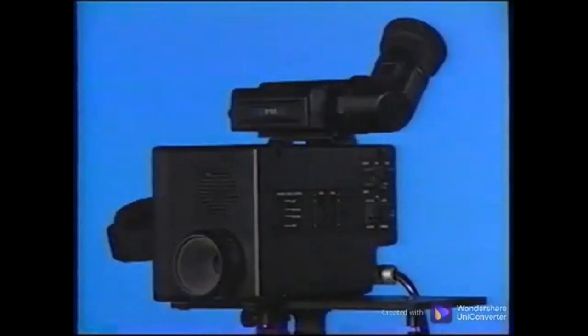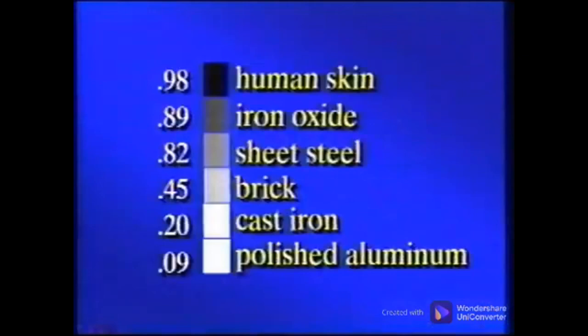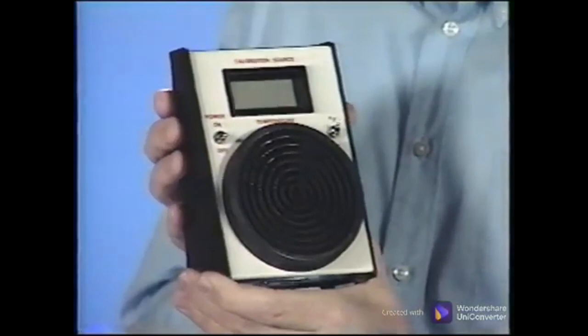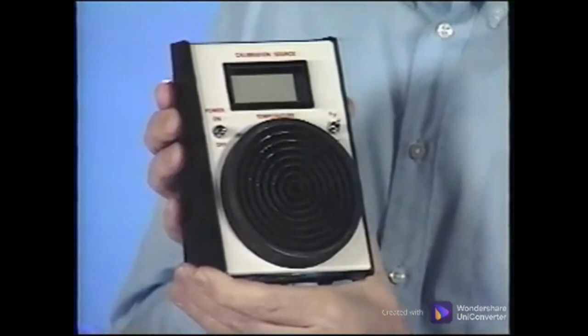The camera allows us to plug in a value for the emissivity, then it will make the correction and display the actual temperature. There are 3 ways to determine the emissivity. One is to use the tables provided by the manufacturer. These tables are really estimations and the least accurate of the 3 methods. The second is to use a black body as a reference, and the third is to use a known temperature for comparison. Either of the last 2 will provide accurate results. Plug in the numbers, and the temperatures will be accurate.